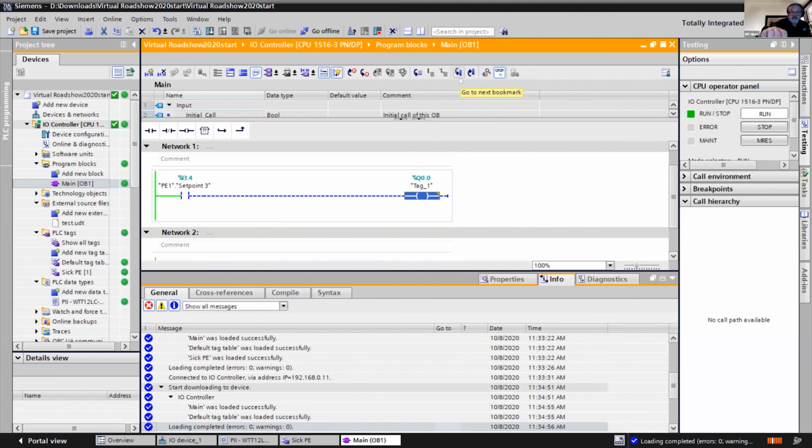So now as I go in and out, my tag names are all working. I'm firing off an output. You get an idea how easy it is to get a tremendous amount of data. Now remember, with IO-Link, we've only got 3 wires running out to our sensor there, and that's just going to be the plus 24, the return 0 volt, and a signal line. And if we were to have the equivalent in digital photo eyes, we need 8 photo eyes, 8 digital inputs, and an analog input to tell us what the full distance is, and all that associated wiring.